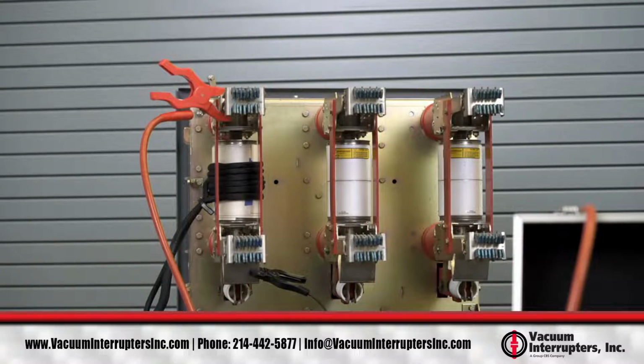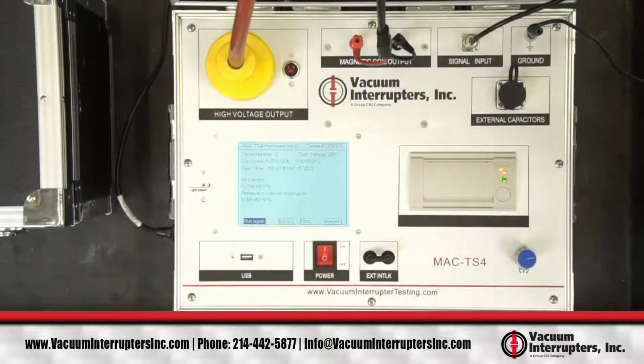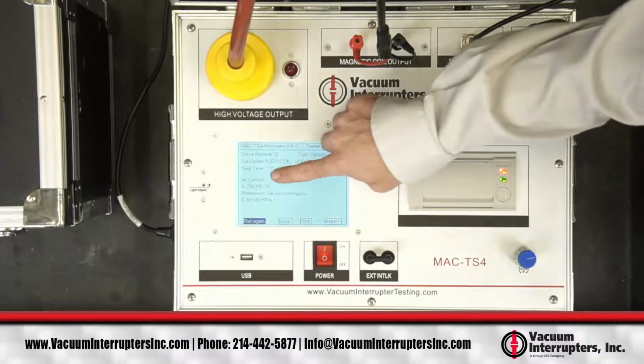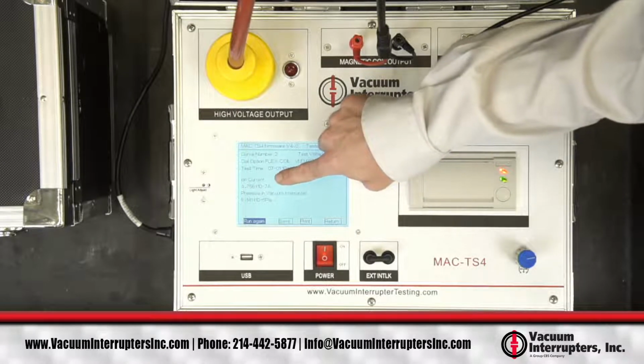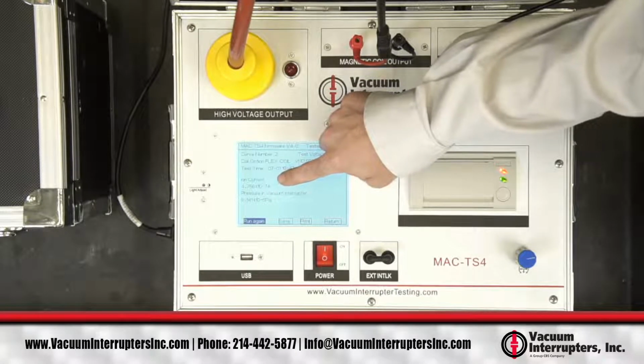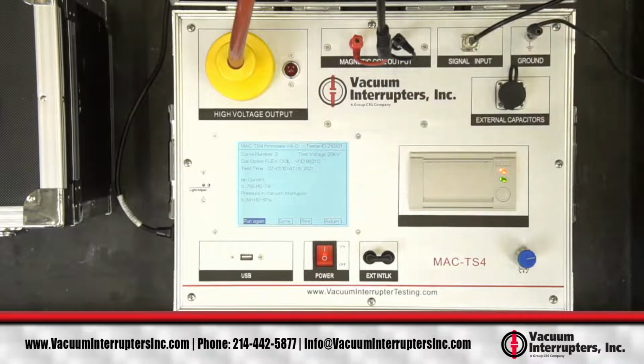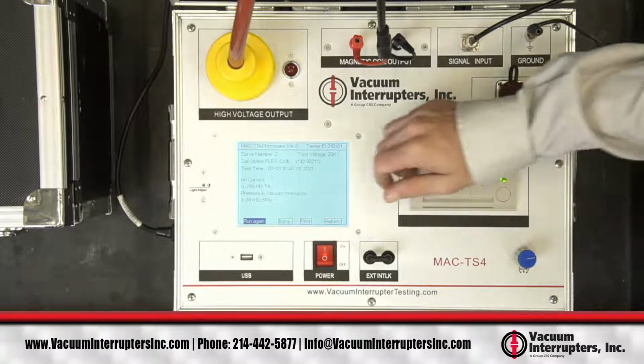So we're fully charged. It's applying the high voltage a second time, and now it's discharging to the magnetic field coil. So that was the entire test. So this is a standard test result that you would get out. You have an ion current. So this ion current is a direct measurement of the current across the VI. So this is, if you had a multimeter connected directly in line, this is what it would read.